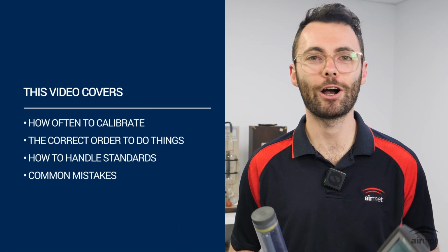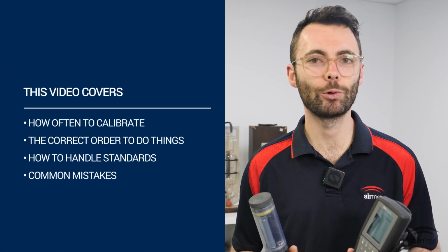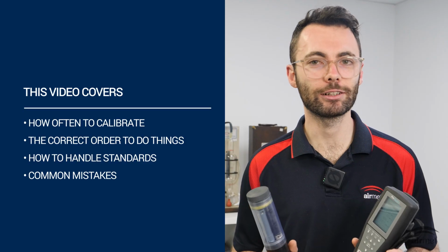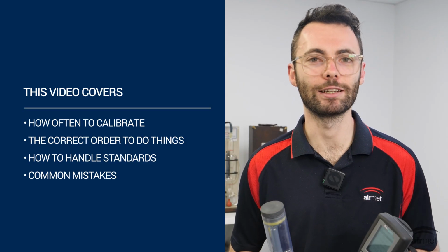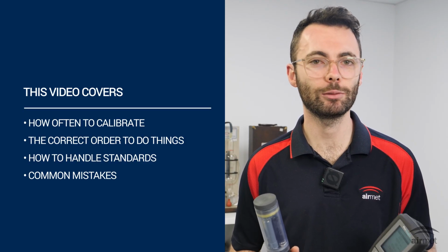Most calibration problems aren't due to sensor failures. They come down to fouling, contaminated buffers, or steps being skipped. In this video, we'll run through how often to calibrate, the correct order to do things, how to handle the standards properly, and a few common mistakes that cause failed or unreliable calibrations.